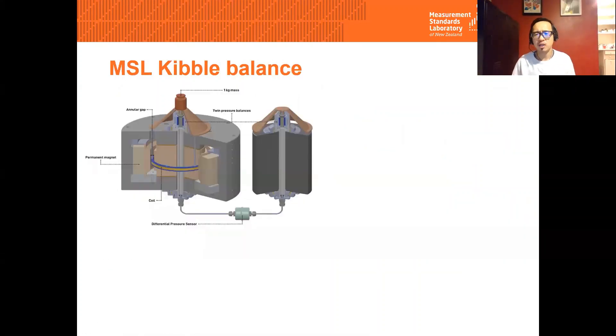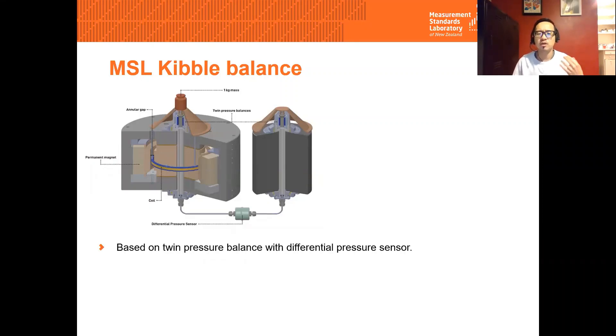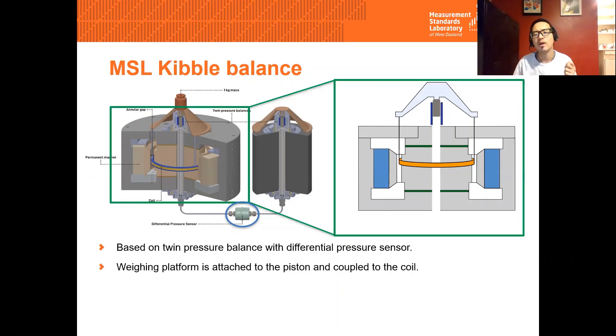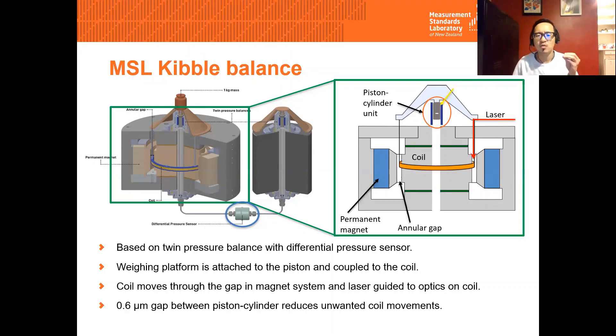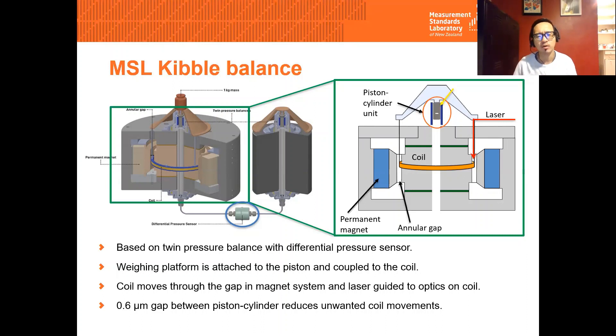Here we describe the MSL Kibble Balance. It is based on twin pressure balances connected to a very sensitive differential pressure sensor, which acts as a force comparator. A weighing platform is attached to the piston of one of the pressure balances and is rigidly coupled to the coil with rods. There is a gap in the magnet system where the coil can move through vertically. A laser beam is guided to the coil to measure the velocity. A very small gap between the piston and cylinder reduces unwanted coil movements. The MSL Kibble Balance is designed to be simpler, more novel, and more economical than others. This is the only Kibble Balance that uses pressure balances — there is no cookbook recipe for it, so there are additional challenges to overcome.